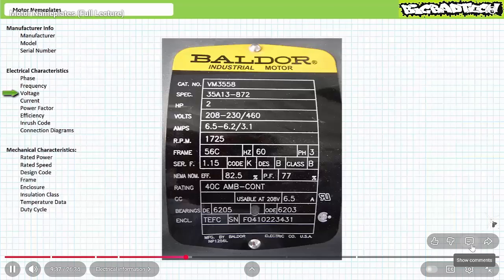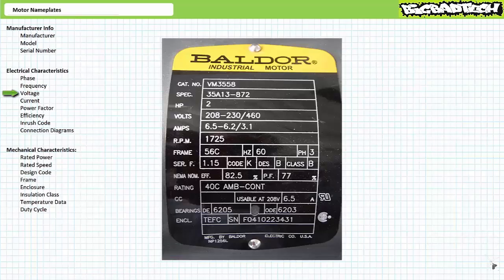Here's an example of a 2-horsepower motor with a dual voltage rating. When windings are wired in parallel for a low voltage configuration, this motor can run at 208 volts up to 230 volts with a 10% tolerance. If, however, the windings are wired in series for a high voltage configuration, this motor can run at 460 volts with a 10% tolerance. Current.